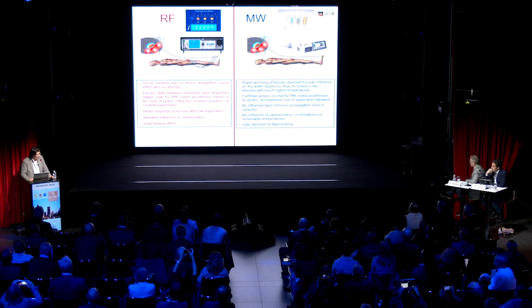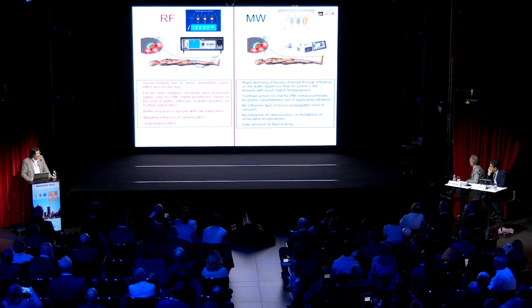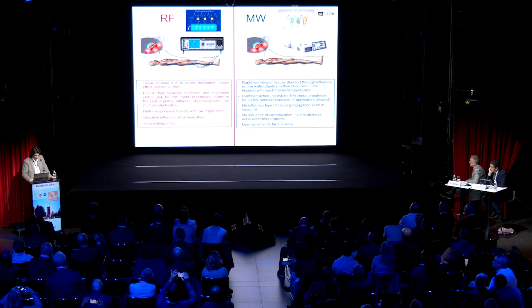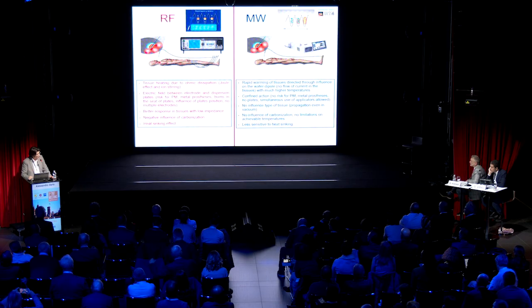With microwave, there is absolutely no influence on the type of tissue. So there is no limitation due to high impedance. The high impedance limits the radiofrequency that does not propagate in tissue without impedance. And there is no influence by the carbonization. Thanks to the microwave, we can obtain higher temperatures with greater speed, and therefore the so-called heat sink effect, the capability of the vessel to take away the heat after the procedure, is less with microwaves.